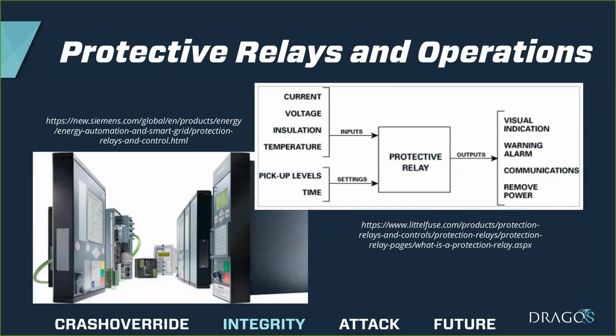Going back to the idea of the Siemens CrashOverride denial of service targeting protective relays—if you're not familiar with electric utility operations, what's a protective relay? Protective relays form a critical protection mechanism for electric transmission, generation, and other operations. Modern digital protective relays are complex, powerful pieces of equipment that continuously monitor various aspects of a given transmission link or link to generation to determine that items are operating within known good tolerances.